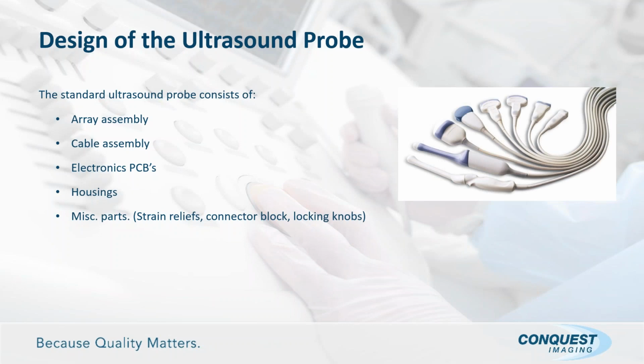So the basic design of an ultrasound probe. These are what I would call the major components, the major sub-assemblies, if you will, of any ultrasound probe. Obviously, you've got an array, and the array itself is an assembly, so we'll touch a little bit on that, but that's got to be made. And the cable is an assembly with all sorts of individual components, not just wires. Obviously, electronics: you've got your circuit boards and the various components on those, as well as the interconnects that have to be on circuit boards to connect either to the array or the cable.